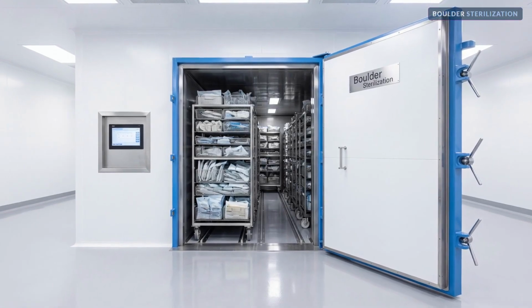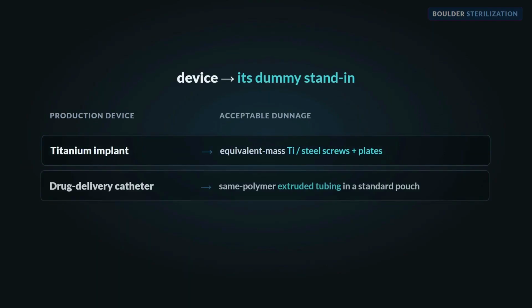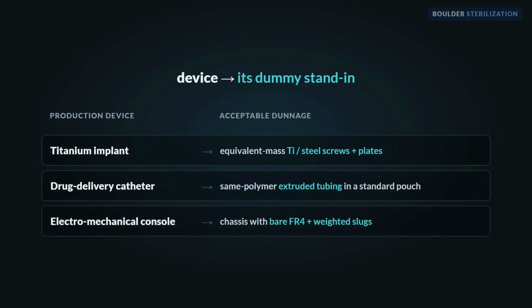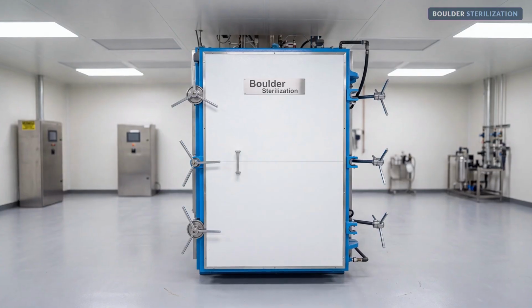So the next time producing your product in Dunnage shows up on your validation timeline, that is what it is. A stand-in load, engineered and documented to prove your real product gets sterilized without burning a fortune in real devices to do it. The equivalency argument, the packaging match, the residual and off-gassing check, all written into the protocol your 510K or PMA depends on. That is easy to get wrong and expensive to redo.